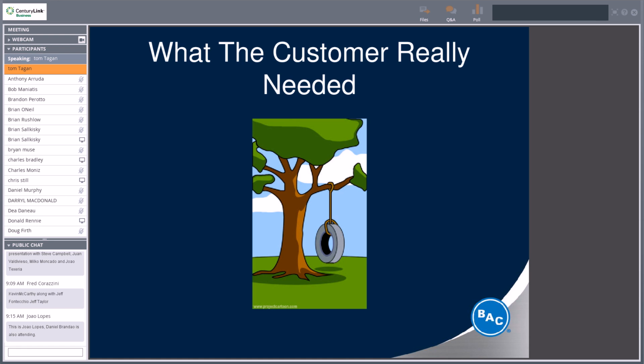To finish up here, we're running out of time. I want to give you guys time for questions. One of the things that this PowerPoint presentation didn't really address is water quality. BAC is not in the chemical treatment business, but they are in the water quality business in the sense that they list the proper water quality guidelines in their O&M. So maybe other than keeping your cooling tower clean and making sure that all the mechanical systems are operating properly, the most important thing you guys can do is chemically treat your cooling tower, whether it's through a traditional liquid chemical system, a solid chemistry system, or a non-chemical treatment system.